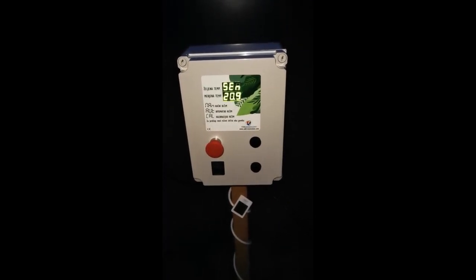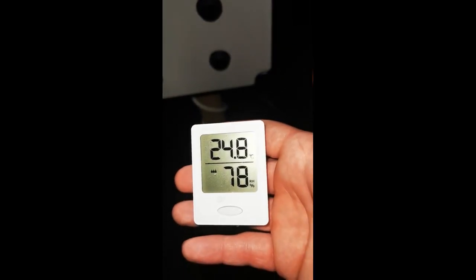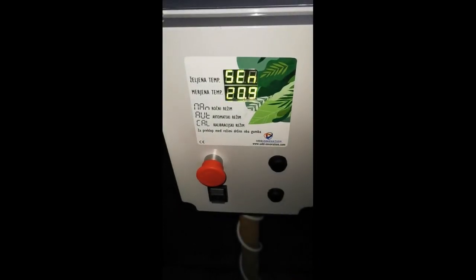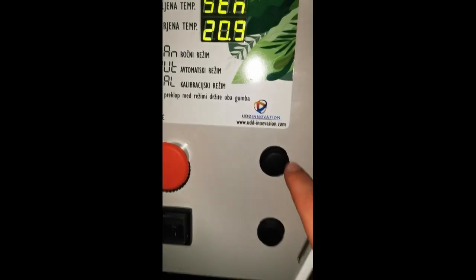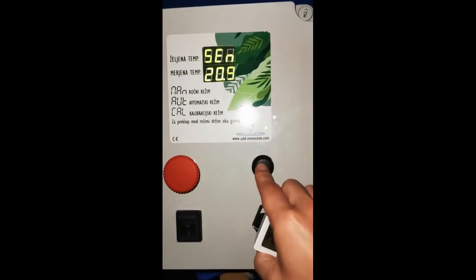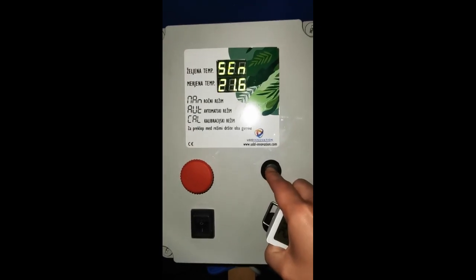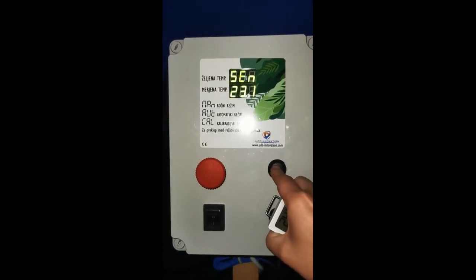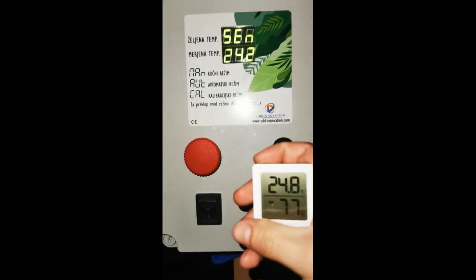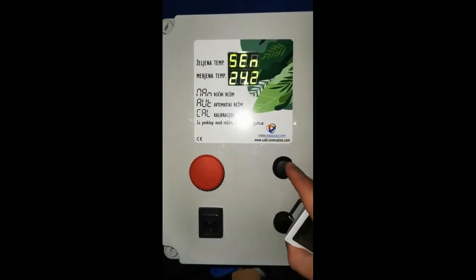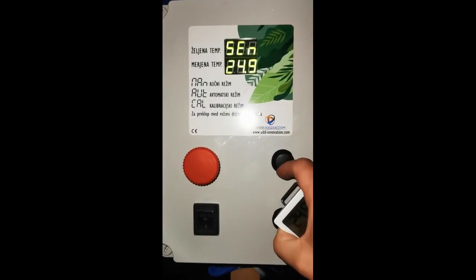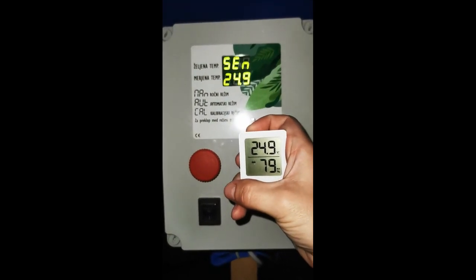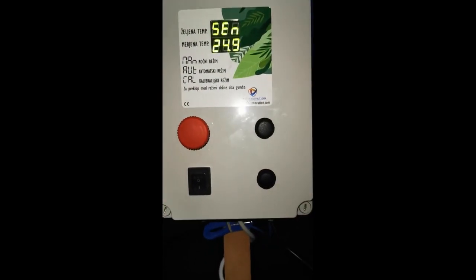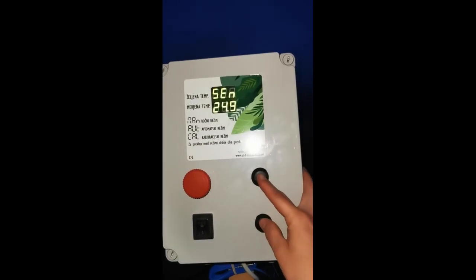If the inscription SEN appears on the upper part of the screen, we are in the calibration mode of the thermometer. Set the same temperature on the box as you read from the reference sensor using the up and down buttons. To save the setting, simply exit this mode by pressing both buttons.